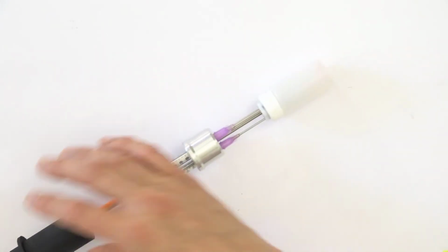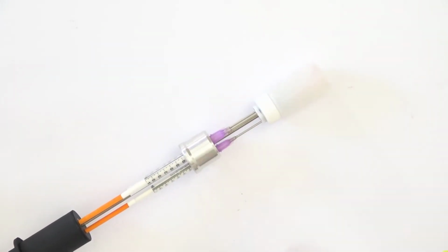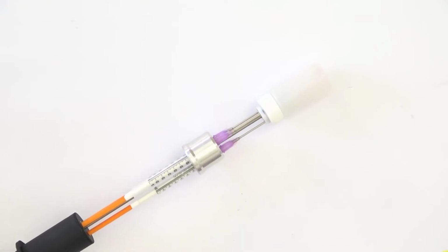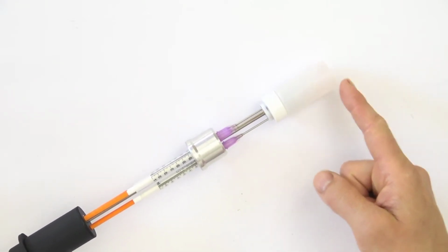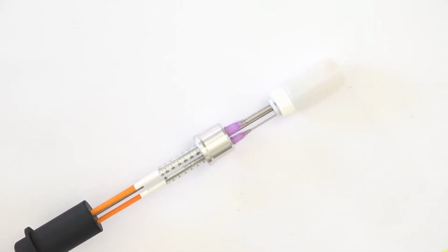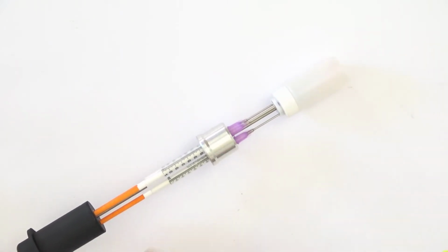So there is a mixer inside the vessel or inside the vial. So we can start the measurement in the calorimeter. This is a good way. And it minimizes the disturbances, but it's not free from problems because there is mixing energy, friction and other things down here. So there will be disturbances also, but this is at least a way to avoid the initial disturbance caused by the sample having the temperature of the room when you charge it.